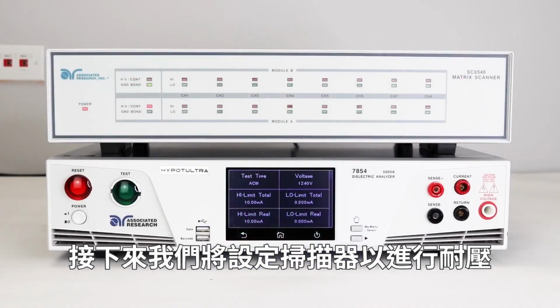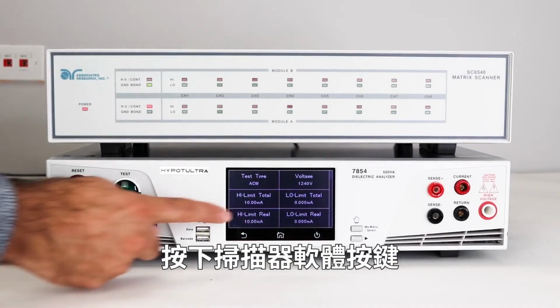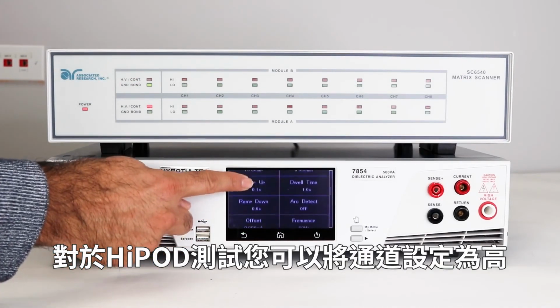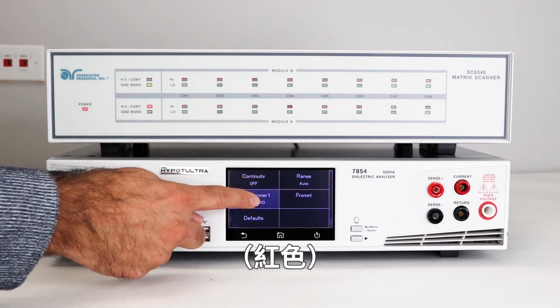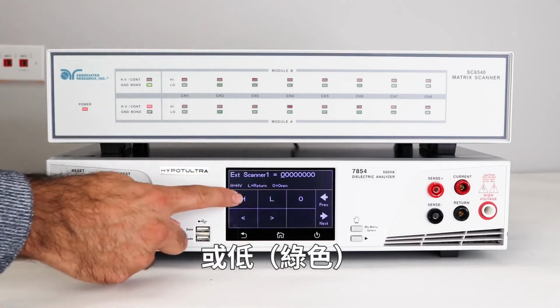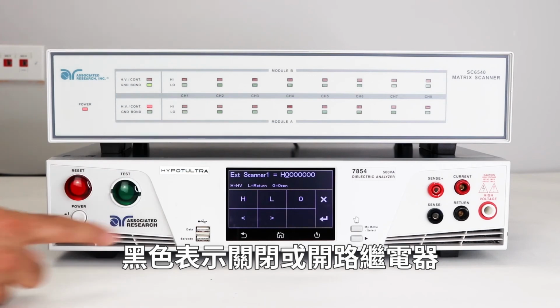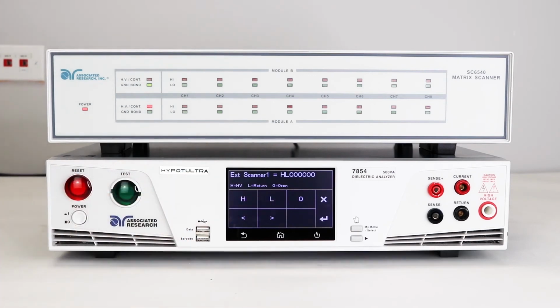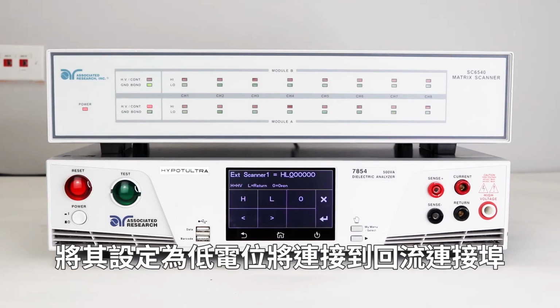Next, we're going to set up the scanners for a hipot test. Press the scanner soft key. For a hipot test, you can set a channel high, which is red, or low, which is green, and black is off, or an open relay. Setting a channel high will automatically connect it to the high voltage port that is connected on the back. Setting it low will connect it to the return port.